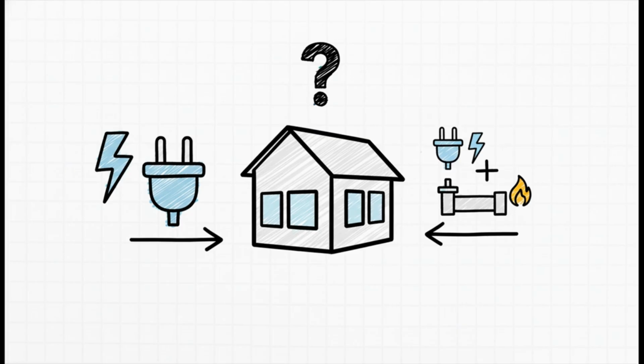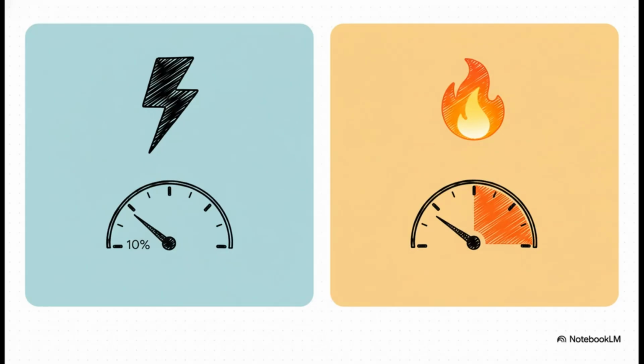Interesting. What about the not all electric side? For not all electric, the multiplier actually drops slightly to 45% of the amount over 325 kVA. But look at the base load. Let me see. 262.5 kVA. Much higher again than the all-electric base of 172.5 kVA. Consistently higher base requirement for the non-electric option, even when the percentage multiplier for the extra load gets closer, or even a bit lower like here. So the code is essentially saying, if you use gas, we need you to build in more guaranteed base electrical capacity right from the start, front-loading it like you said.